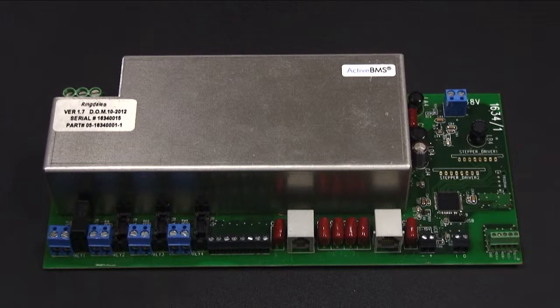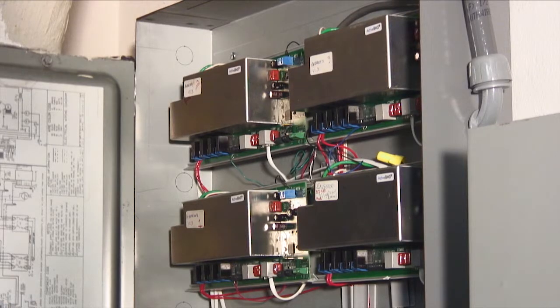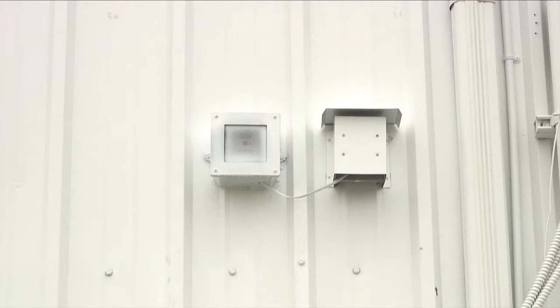Adapting Active BMS to conventional electrical devices is easy using a relay controller board. Each relay controller can either directly control small loads or operate a contactor or relay to switch higher loads or three-phase loads. The relay controllers are connected to an LSC controller for server or LSM device management. A daylight sensor connected directly to the relay board or via an LSC can be used to trigger relays to turn on contactors for outside conventional or non-dimmable lighting.